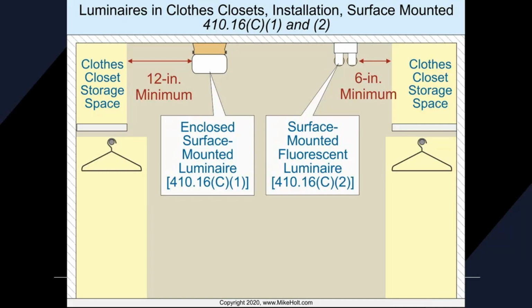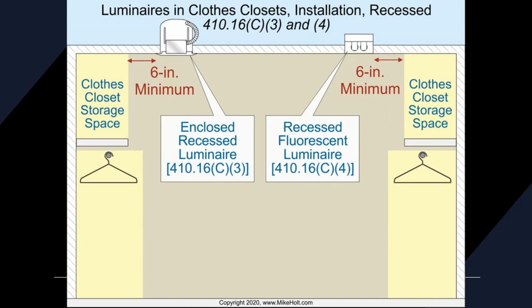All right, luminaires in clothes closets, installation surface mounted, 12 inches from clothes closet storage spaces. If you have a fluorescent, it needs to be 6 inches away, minimum. So a lot of times there's like a misnomer out there. I'll run into guys, especially newer guys, that say, oh, I got an LED, I can put it anywhere in the closet I want. That's not true. Or I got a fluorescent, I can put it anywhere in the closet I want. That's not true. You can't stick it directly over a clothes closet storage space for a fluorescent light. Recessed light also needs to be 6 inches away.